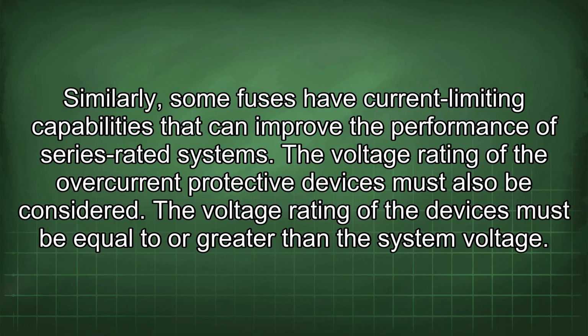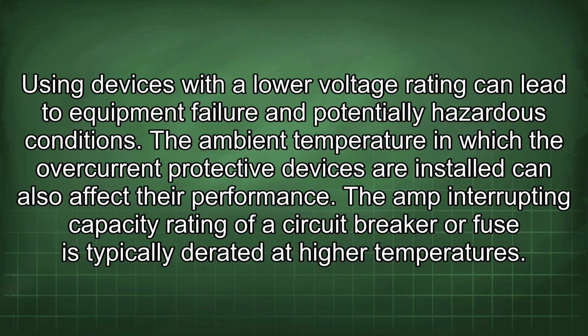The voltage rating of the overcurrent protective devices must also be considered. The voltage rating of the devices must be equal to or greater than the system voltage. Using devices with a lower voltage rating can lead to equipment failure and potentially hazardous conditions.